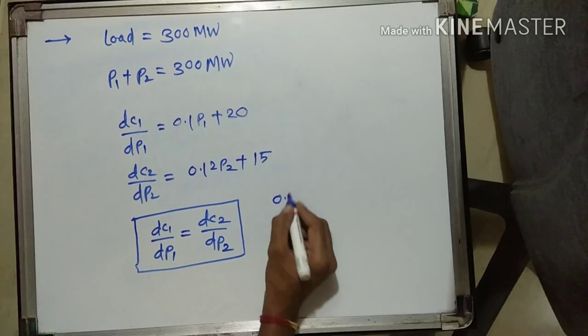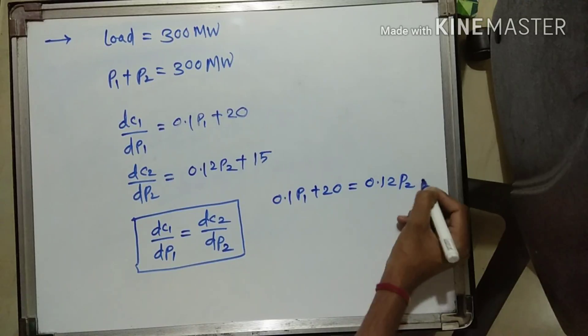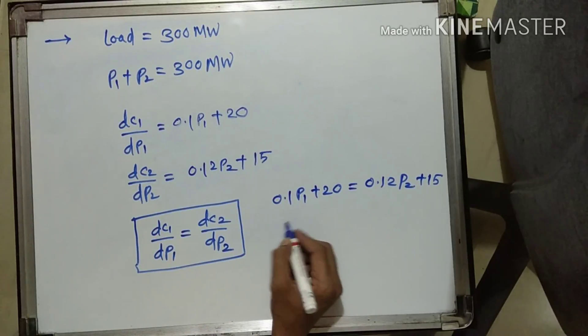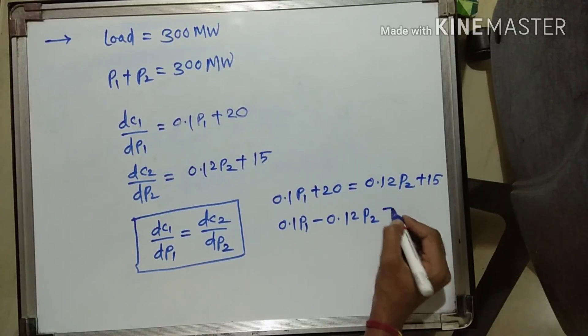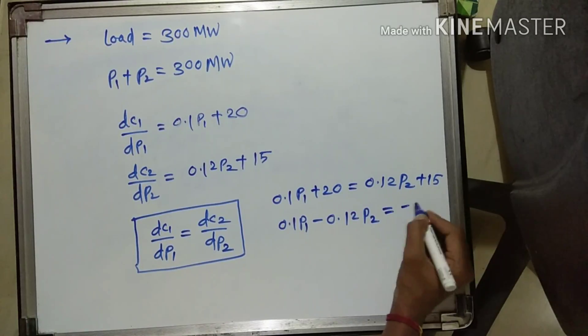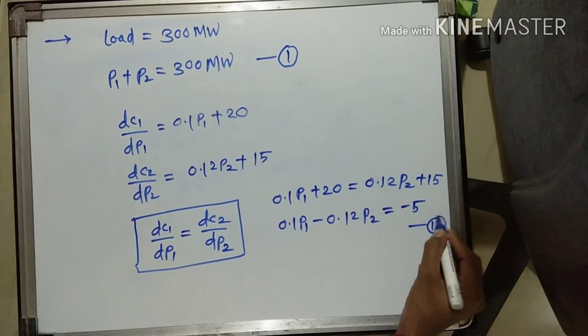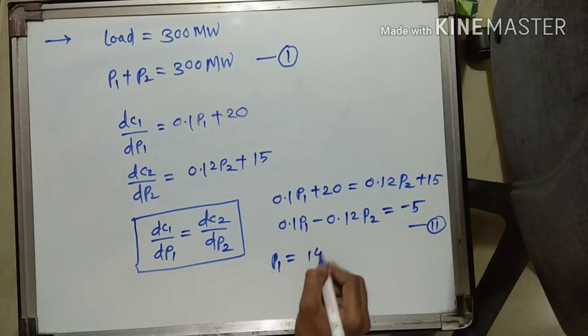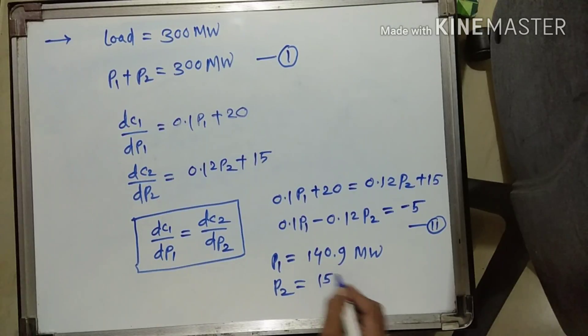It becomes: 0.1P1 + 20 = 0.12P2 + 15. Rearranging, taking P1 and P2 to the left-hand side: 0.1P1 − 0.12P2 = 15 − 20 = −5. This is equation 1, and P1 + P2 = 300 is equation 2. Solving equations 1 and 2, we get P1 = 140.9 megawatt and P2 = 159.09 megawatt.